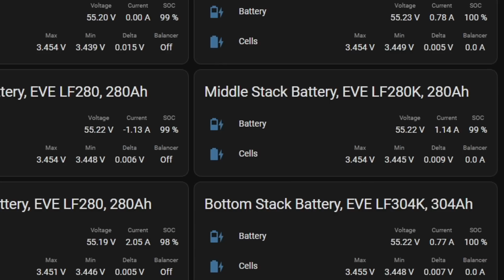A second thing to tweak here is to adjust the timer for your reset of 100% state of charge if you have JK inverter BMSs connected, because they only reset after the absorption timer in the BMS has run out. If this sits on 30 minutes and you're only absorbing for 20 minutes, it will never reset to 100%. So you probably need to take this down to only 10 minutes or so.